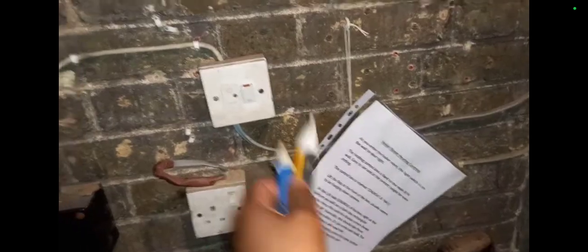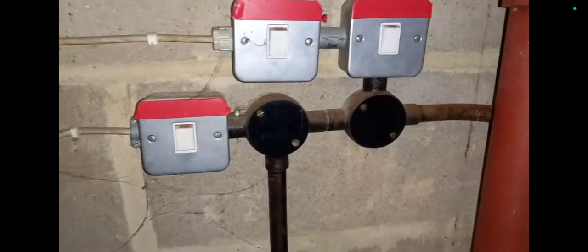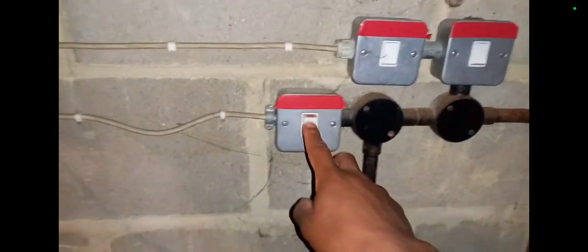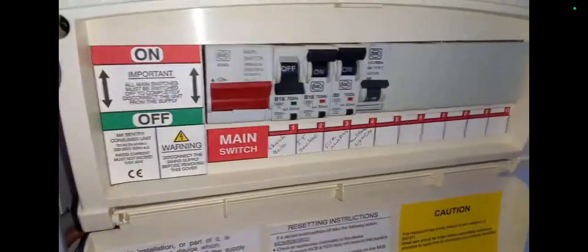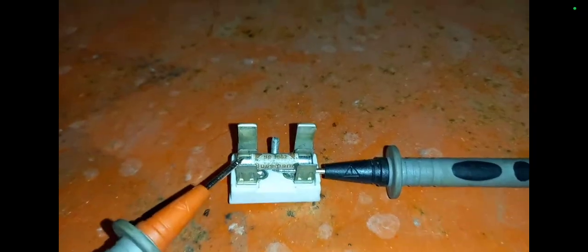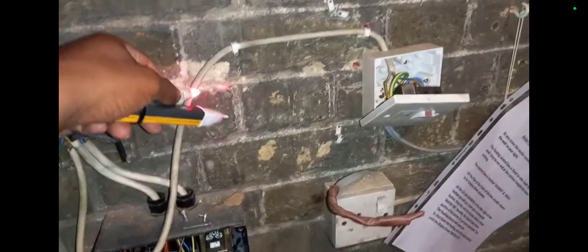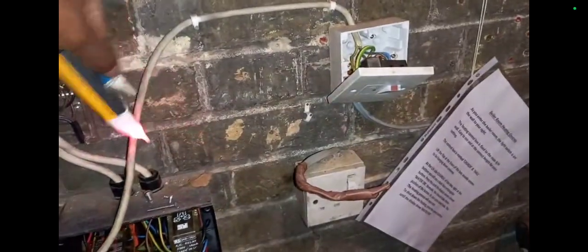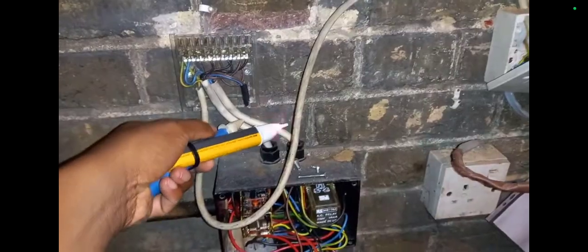I was carrying out checks to see if I could get power to it, but for some reason there was no power. So I switched off some of the pumps and the boiler and different things because a breaker was down. I flicked the breaker up, found a fuse in my van, checked it and it seemed fine. I managed to get power through, but the only way I could get it to stay on without tripping the breaker was by removing the programmer.